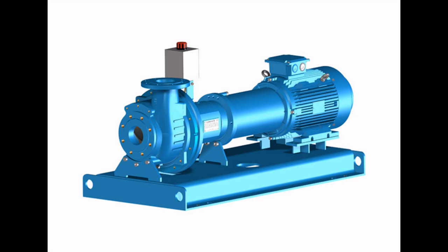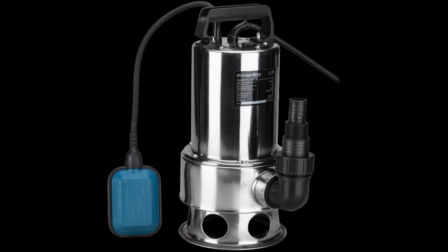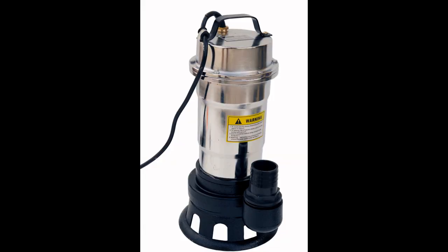4. How do we choose a surface pump? We need to know the suction depth as precisely as possible. For suction from a maximum of 8-9 meters, a surface centrifugal pump can be chosen. If the pumping depth is greater than 8-9 meters, we will choose a surface pump with an ejector. We have to consider the supply route to consumers, both horizontally and vertically.